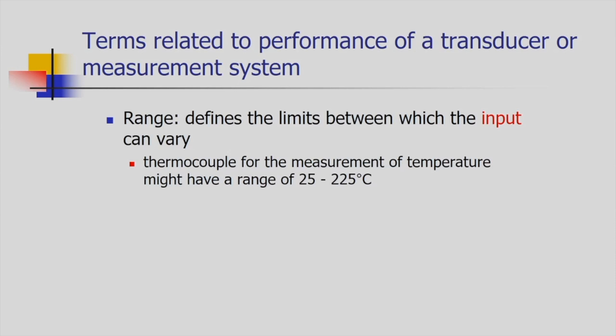The first term is range. Range defines the limits between which the input can vary for that sensor. If you consider a thermocouple used to measure temperature, and its range is from 25 to 225 degree Celsius, that means the minimum temperature the sensor can measure is 25°C and the maximum is 225°C. So the range is 25 to 225 — the limits between which the input can vary.